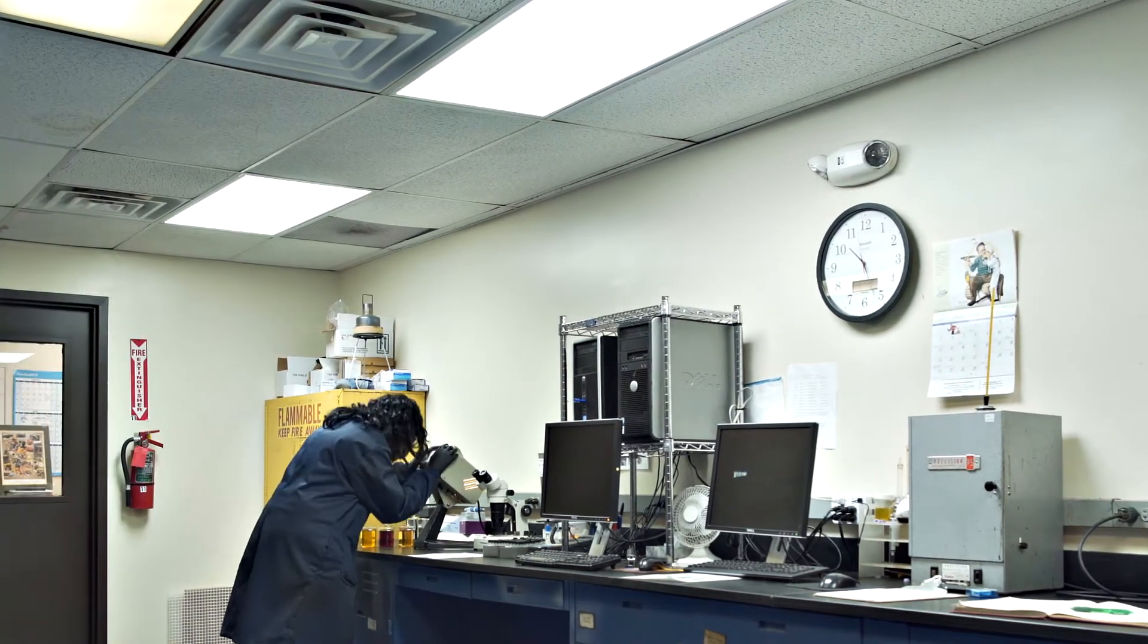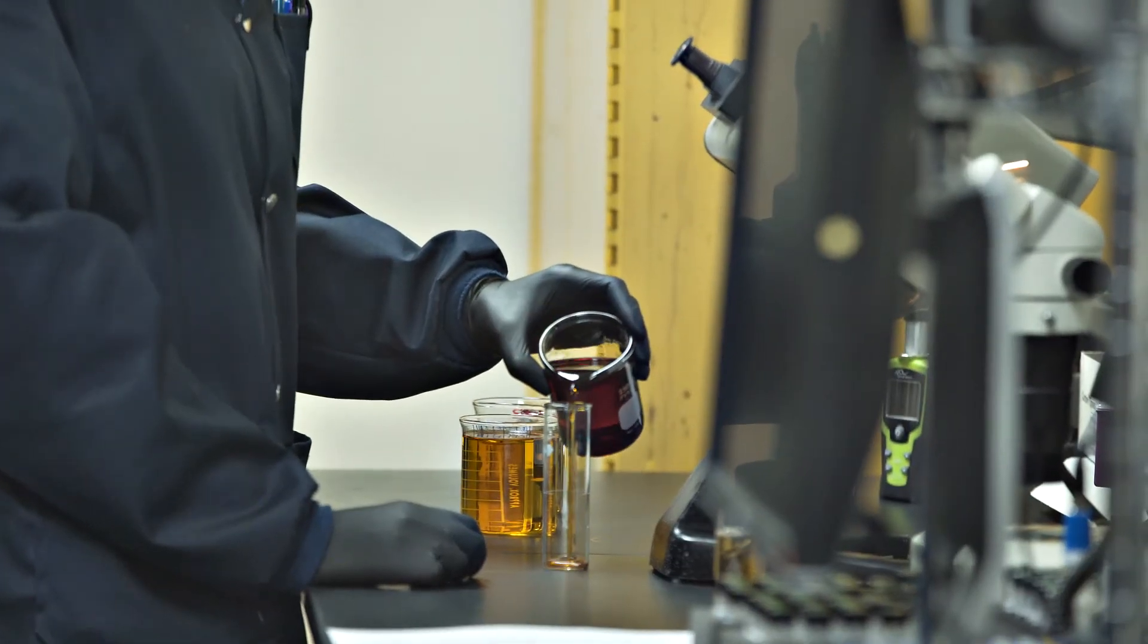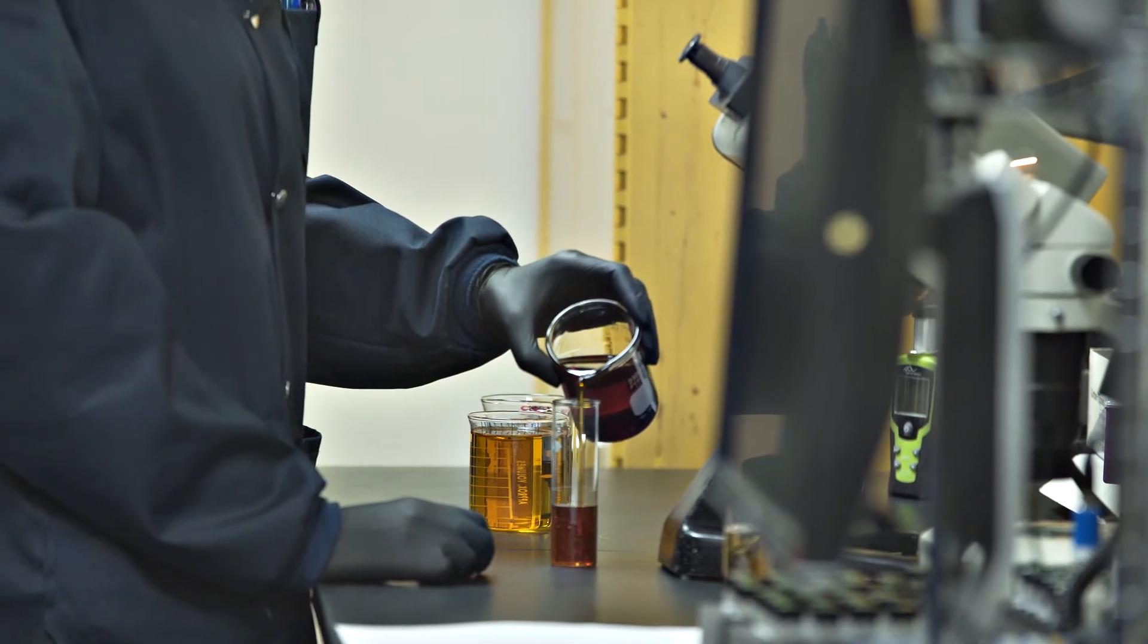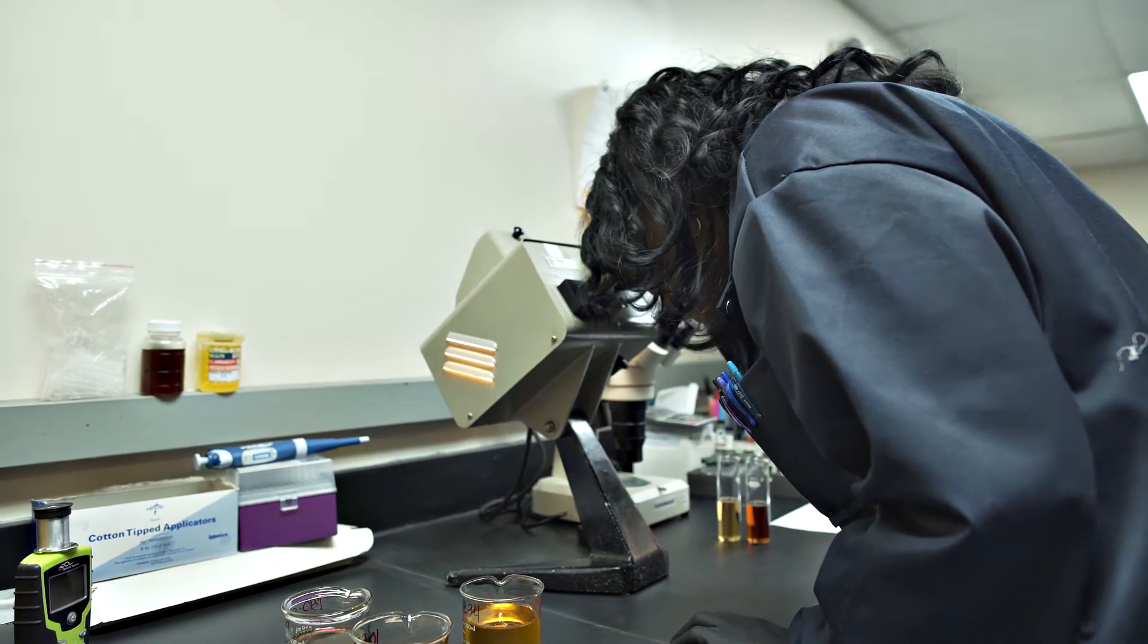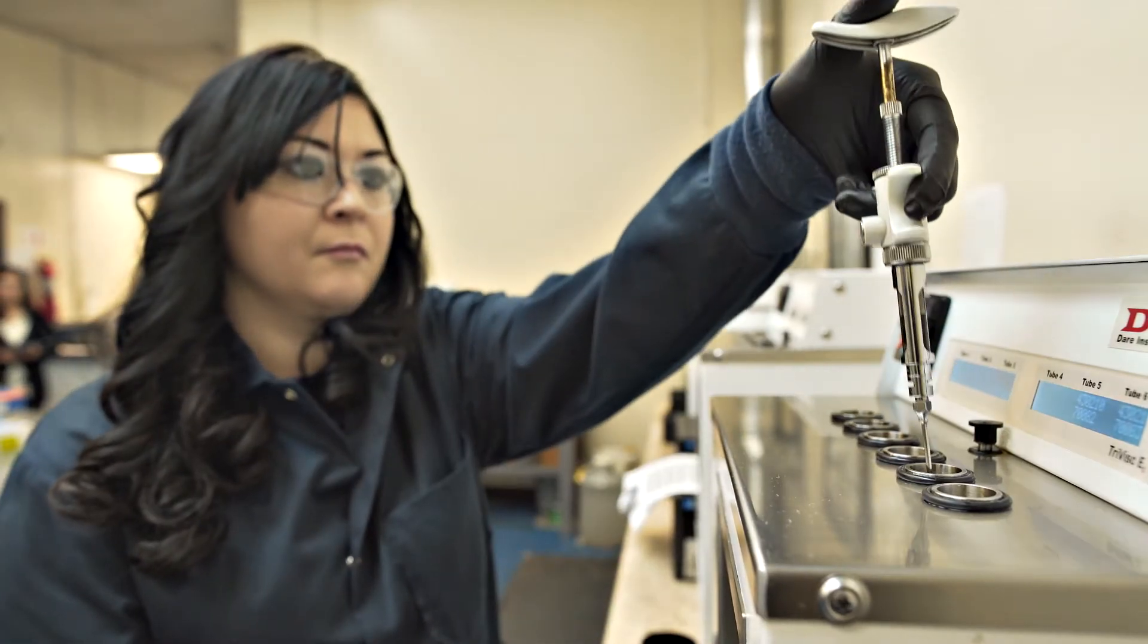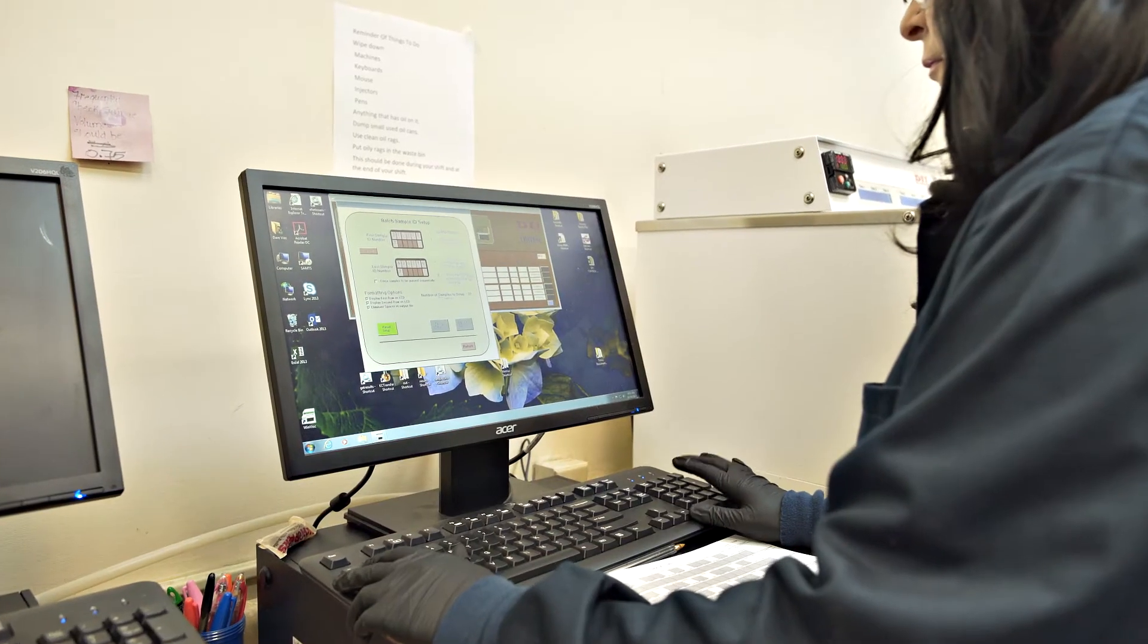Routine testing includes appearance for a general qualitative inspection of the turbine oil fluid. Color is a qualitative indicator of fluid condition. Viscosity to ensure proper lubrication in fluid film for operating load, speed, and temperature range.